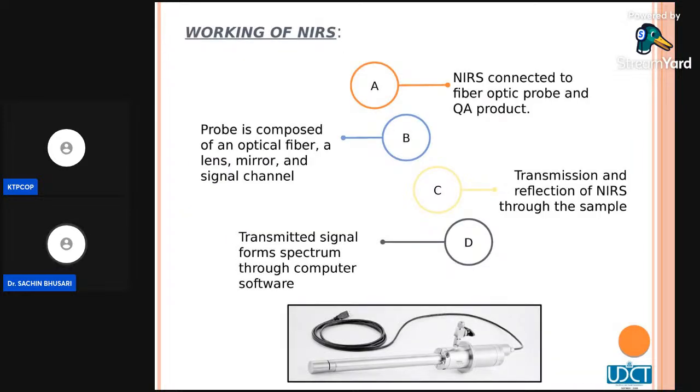Now, the working of NIR. This is the classical slide, a very important slide. Now you can see the difference. Now it is probe based. So you can use the near IR probe, a handheld device, and you can take out this probe. You can take this probe to your API container, to your formulation, any platform. You can take this probe with you.